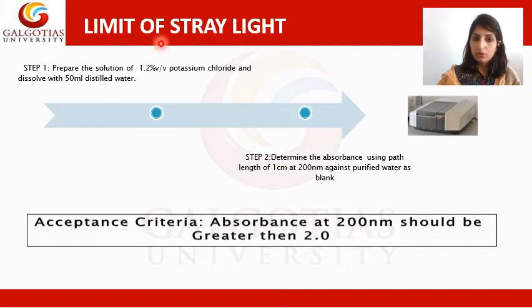To check the stray light present in your instrument, you will prepare a solution of 1.2% weight by volume potassium chloride and dissolve it in distilled water. Second step, you will measure the absorbance of your 1.2% potassium chloride solution in a 1 centimeter path length cell at a wavelength of 200 nanometer. The absorbance that you are getting should be more than 2. The absorbance at 200 nanometer should be more than 2. If it is less than 2, then stray light is present in that instrument. Basically, stray light is producing a negative deviation, so the absorbance value that you get is lesser.